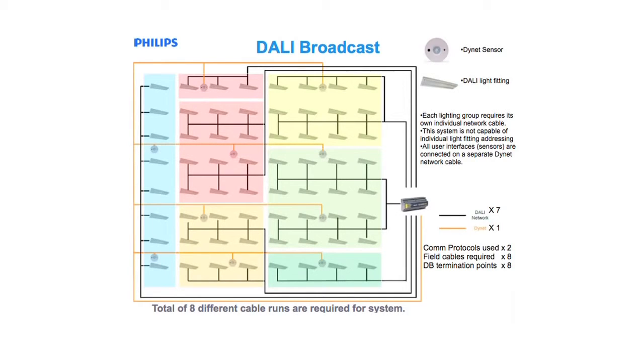Each of the lighting groups in the individual areas needs to be wired back to the load controller separately. This is also the Dynet cable shown in orange, which needs to be wired to each of the Dynet sensors. Each sensor issues instructions back to the load controller via the Dynet network. Load controllers will respond to sensor requests back to the ballast connected to it. This system requires a total of 8 different cable runs to achieve the required functions of this area.